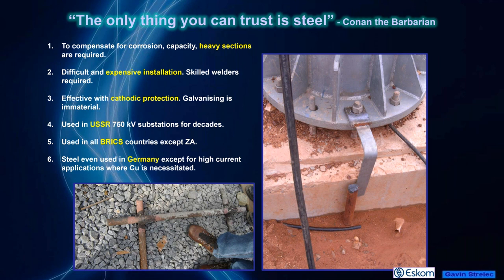To come up with a technical solution using steel, we have to go for very heavy conductor cross sections, leading to expensive installation. We also need skilled welders, and this is only really effective if we employ cathodic protection. Steel has in fact been used for several decades in the former Soviet Union, quite effectively, and is used in all the BRICS countries except South Africa, interestingly. Steel has even been used in Germany, except in applications where the current is so high that steel won't suffice at practical cross sections.